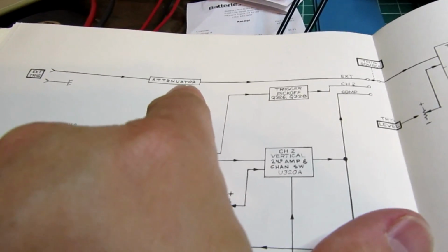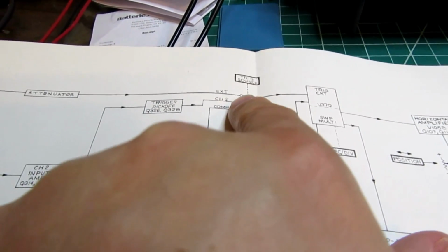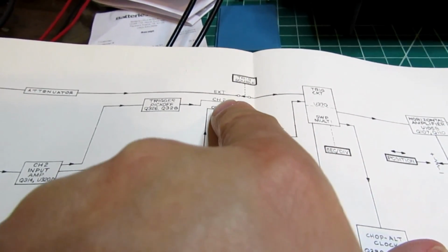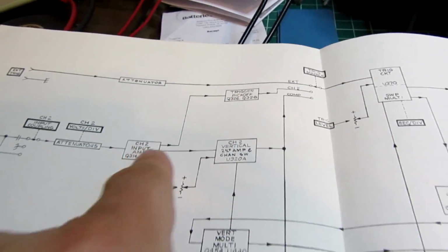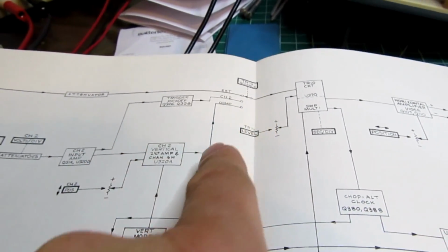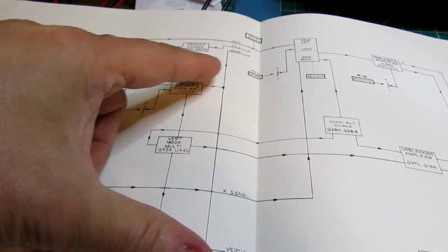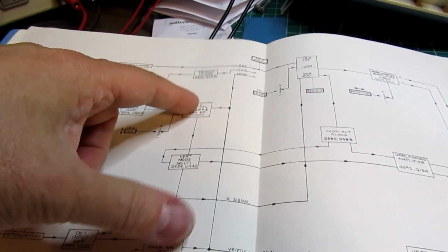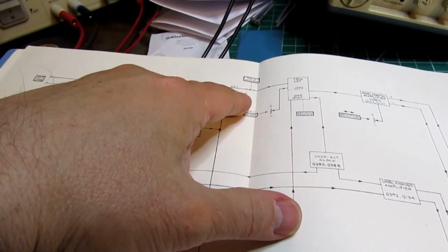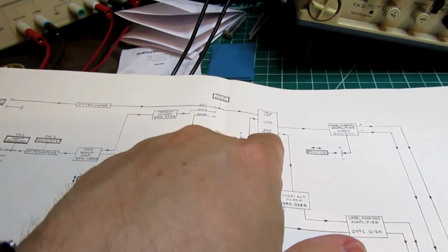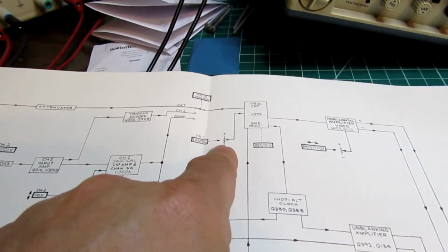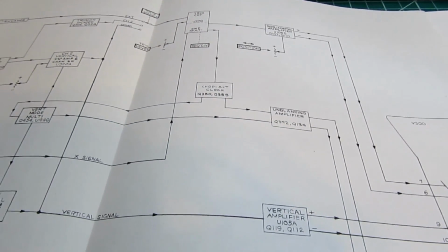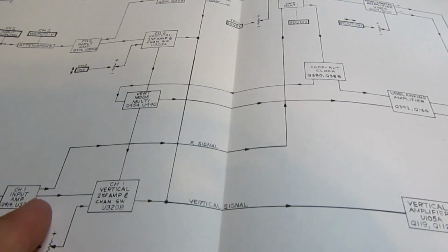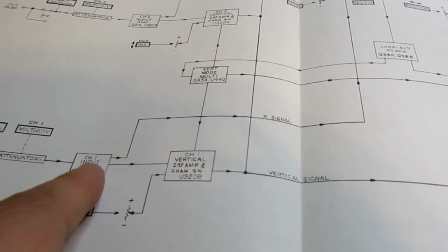And then you've got your external trigger, which has an attenuator, and here's your trigger source where you can pick external. You can pick the channel 2 where it's taking it straight off the channel 2 amplifier, or you can pick the composite source, which, as I mentioned before, is taking the common bus signal after the 2 vertical amplifiers, and whatever's on there is used as the source of the trigger signal. Then you've got your basic trigger circuit with the trigger level potentiometer, and if you're in XY mode, then it also taps the other channel off to come in here.